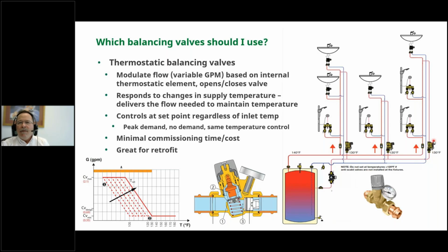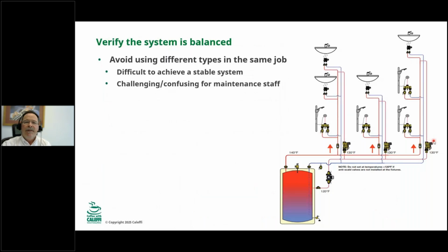You don't really want to mix and match different types of balancing valves. I guess you can, but it would be more difficult to achieve a stable system, and I wouldn't want to be the maintenance guy who has to go around and service valves if some of them are thermal and some of them are manual that require a differential pressure tool. Try and stick with the same type of valve throughout the system.